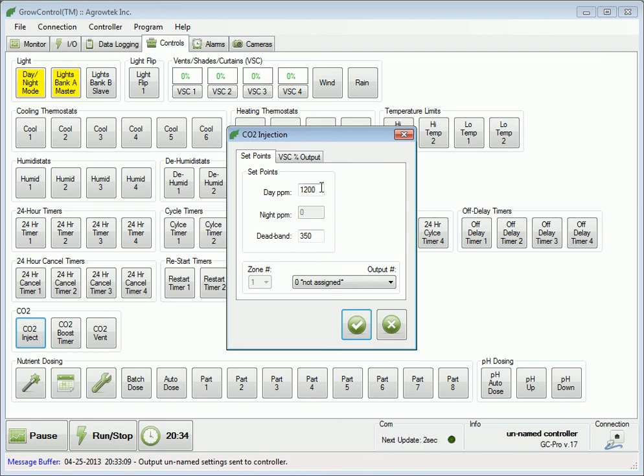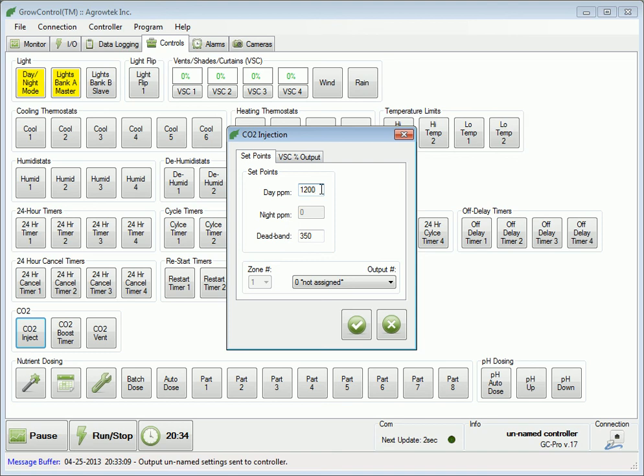Day PPM is the target PPM level that the controller will attempt to maintain. If CO2 is below this level, the controller will activate the CO2 output. Once the CO2 level has been achieved, the controller will turn the CO2 output off. If the PPM level drops below the target amount by the dead band, it will turn the CO2 output back on until the target is achieved again.